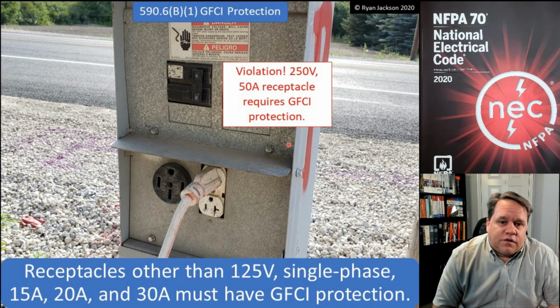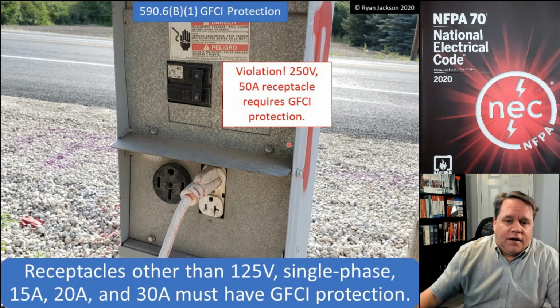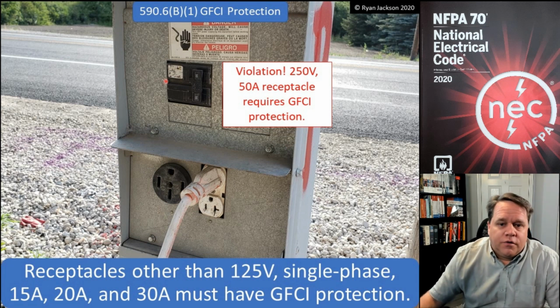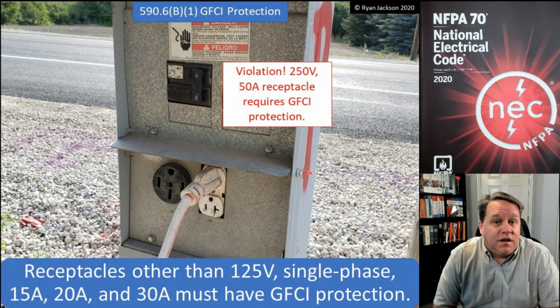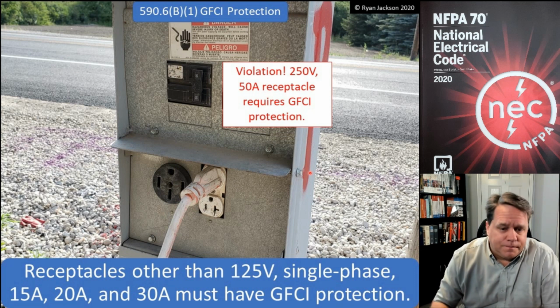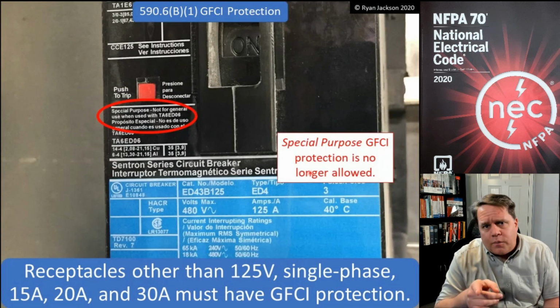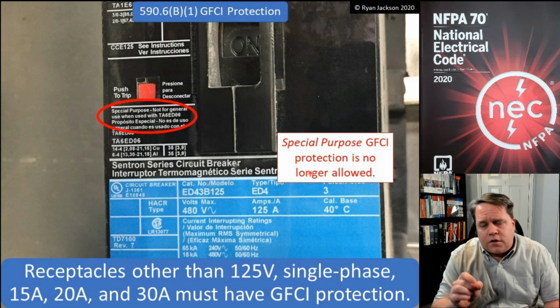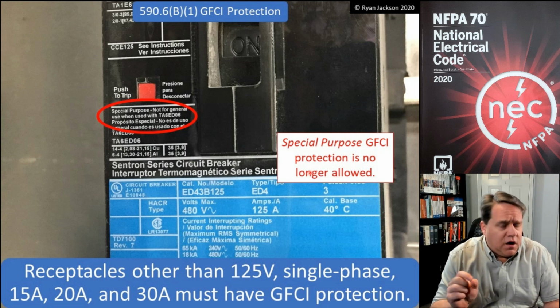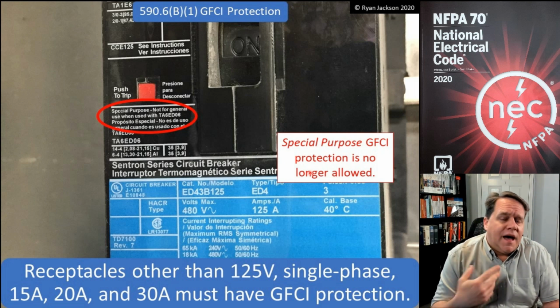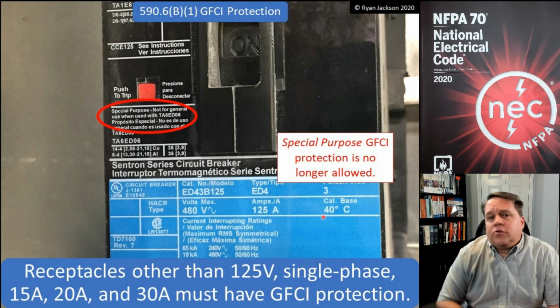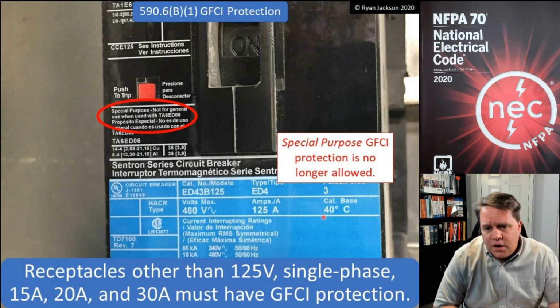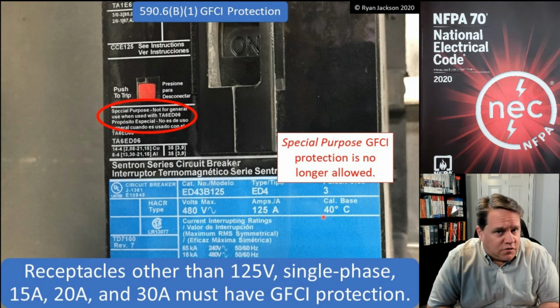So looking at this photograph here, this would be a violation. Right here we've just got a regular old 2-pole 50, and we've got a 50 amp receptacle, and yeah, that's a violation. That thing needs to have GFCI protection. I want to point out something that was in the code for only 3 years. In the 2017 code, they added language about what we call special purpose GFCI protection, and then they took it right back out in the 2020.